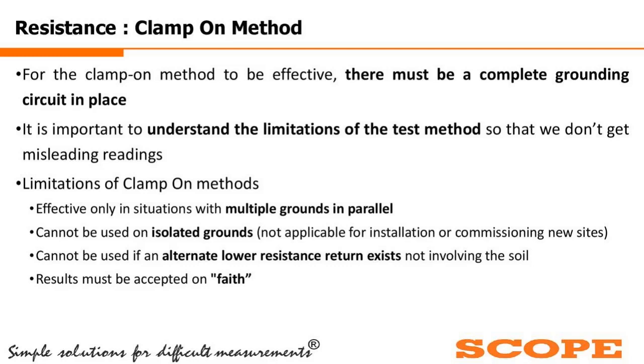Limitations: this is effective only in situations with multiple grounds in parallel, because only then will I be able to get a loop current, and until a loop current is there, we cannot use the stakeless method or clamp-on method. It cannot be used on isolated grounds; it is not applicable for isolated ground conditions. Means when I am going for a new installation or commissioning in new sites, I can't use this, because there the ground might be isolated, it is not yet connected.